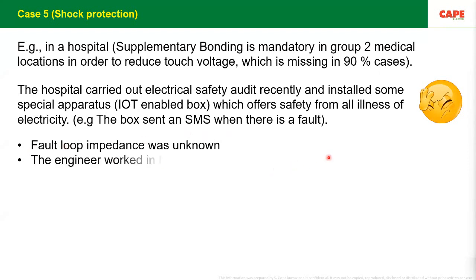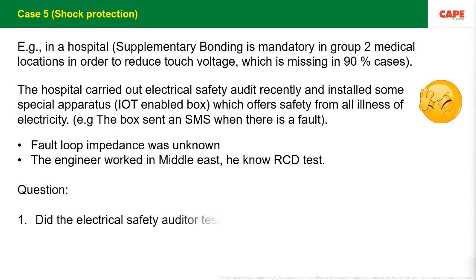Then for this particular engineer, of course, fault loop impedance was a little bit unknown. But this engineer or supervisor has worked in the Middle East. Then I asked, have you carried out the RCD test? Because the RCD test is quite mandatory in the Middle East. Then he told me, no, we didn't. Then I asked, okay, has your electrical auditor done the RCD test? No, the electrical auditor also didn't do the RCD test. Then my next question was, in that case, what did the electrical auditor do? Then he told me he recommended a few chemical earthings.